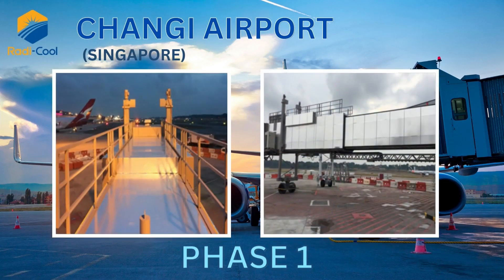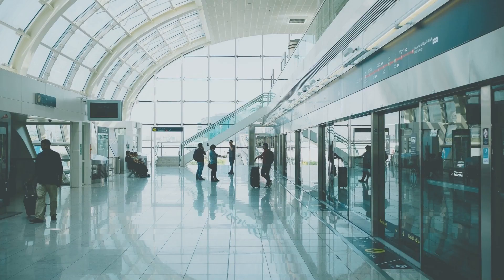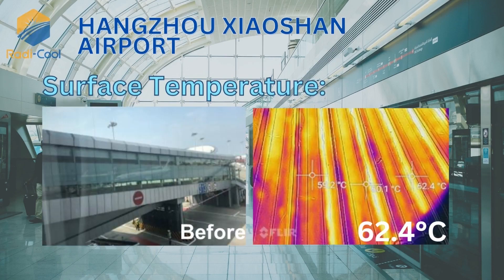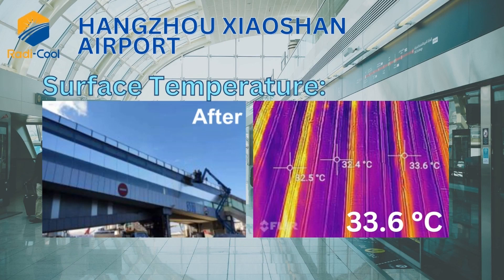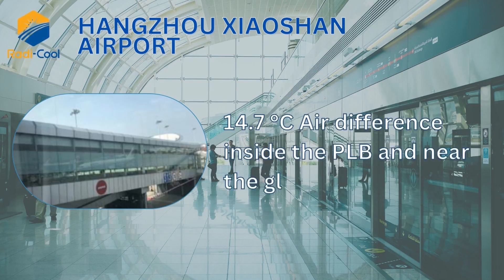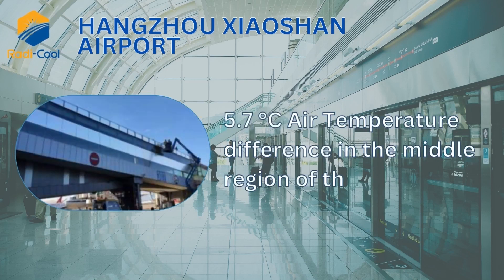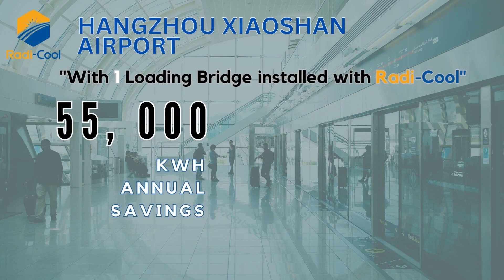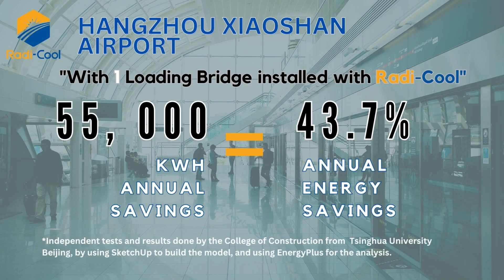Great results made the airport management decide to fully install Radi-Cool on all terminal glass window panels. Hangzhou Xiaoshan Airport: surface temperature before — 62.4 degrees Celsius; after — 33.6 degrees Celsius. A 14.7 degrees Celsius air temperature difference inside the PLB near the glass, and a 5.7 degrees Celsius air temperature difference in the middle region of the PLB. With Radi-Cool applied on only one loading bridge, the airport achieved 55,000 kWh annual savings, translating to 43.7% annual energy savings.